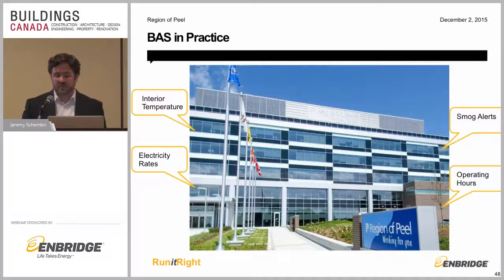On the environmental piece, we've tied our system into smog alerts. So when we get announcements from, I believe it's the feds, but it might be the province, I'll have to check. It's either Environment Canada or the province, and we're being told that there's a smog alert, we do change our set points. Typically that happens in the summer, so we have an automated response that will let our set points go up a couple degrees, just to do our part in that.